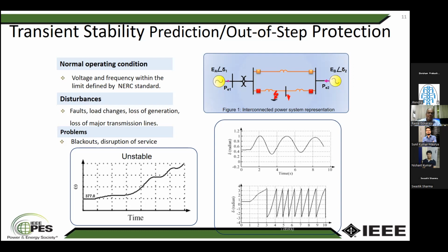So around 270 to 360 degrees, that is the North American practice. In Europe, about two pole slips are allowed. And the practice in Asia, depending on the vendor, could be different. For example, I'm told for some of the hydro generators in China, they allow up to 8 to 10 pole slips, and the gas turbine generators.